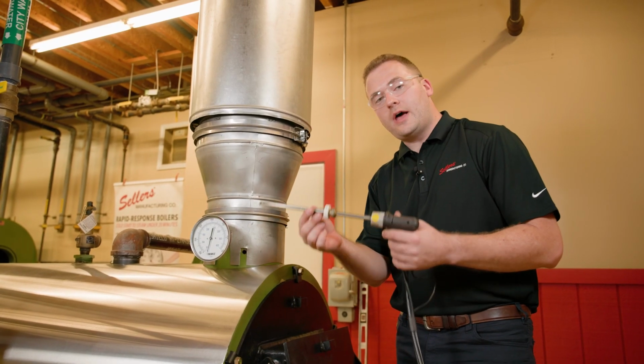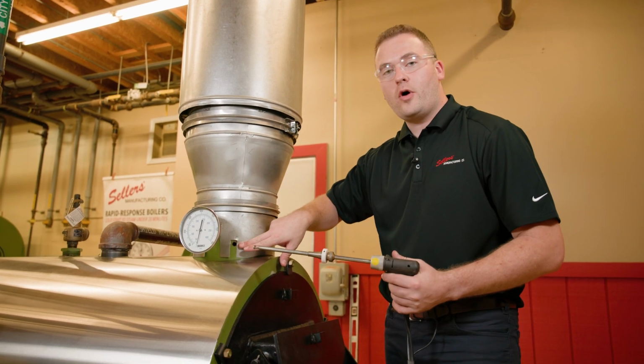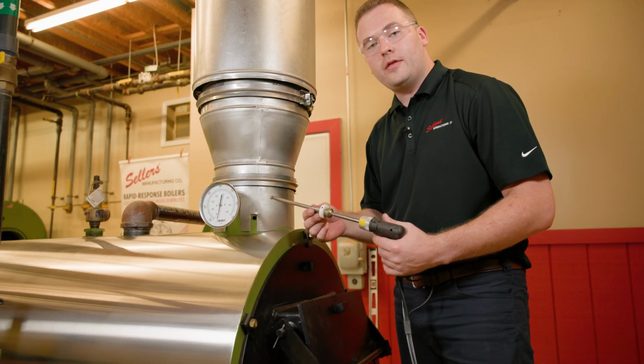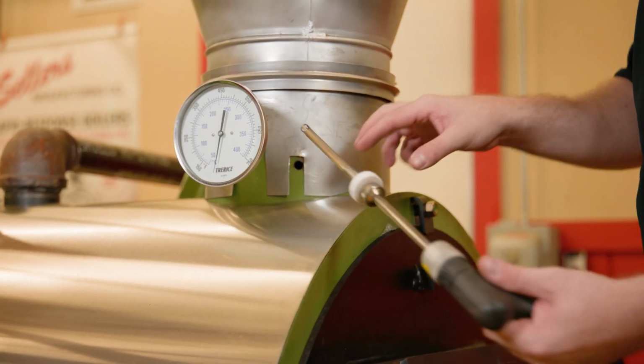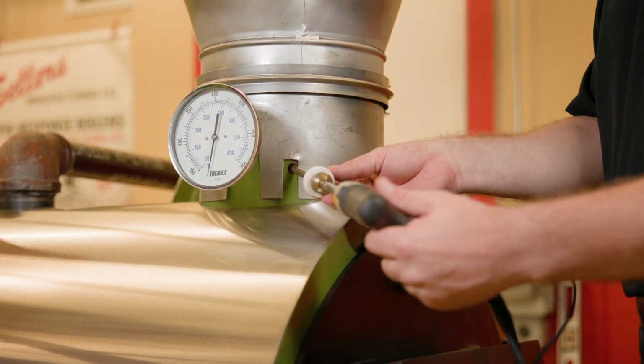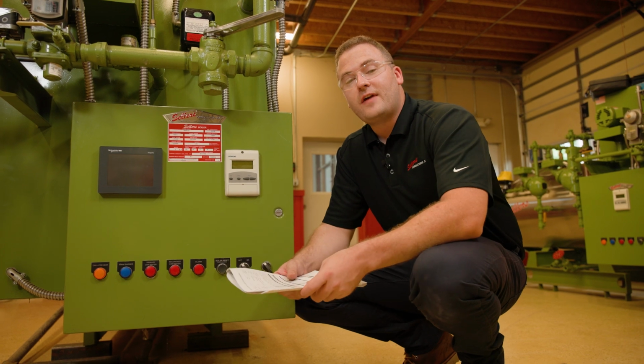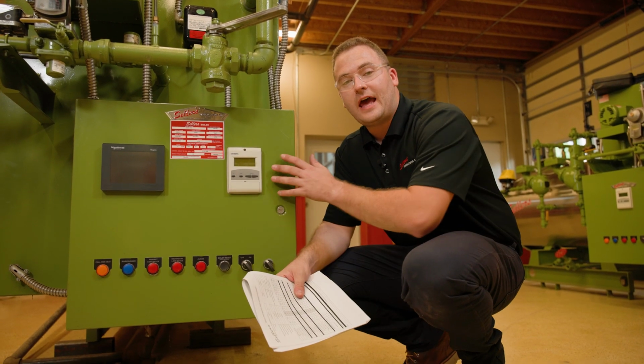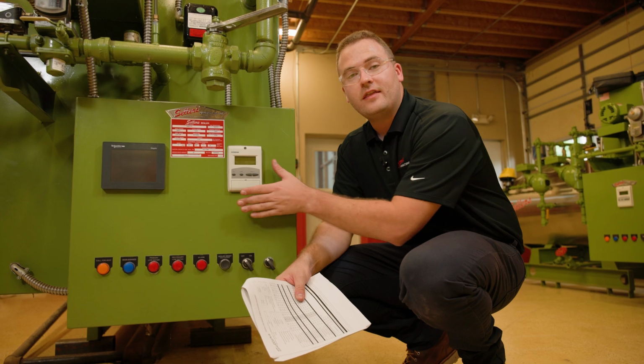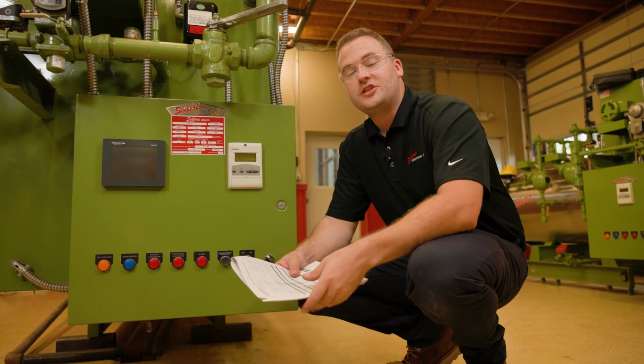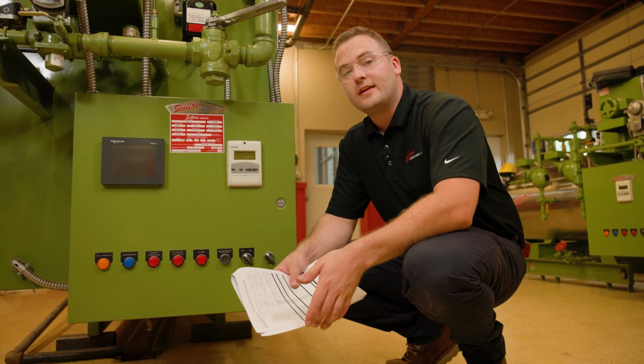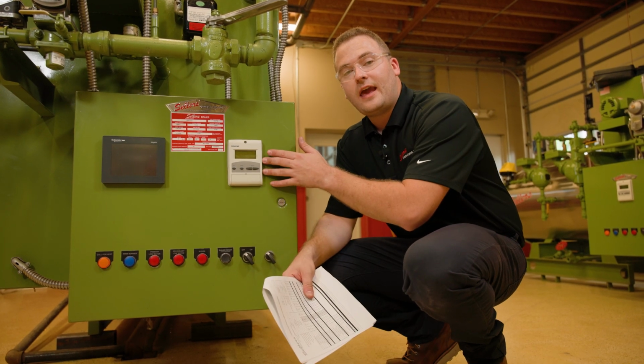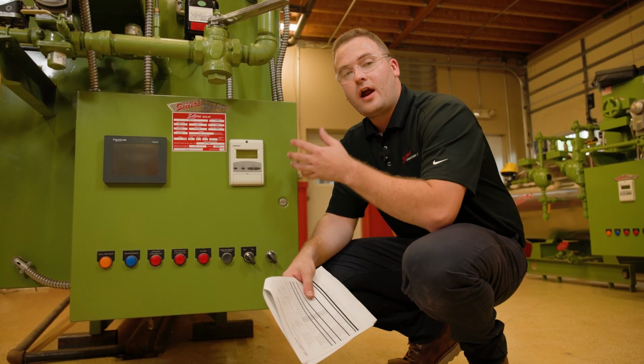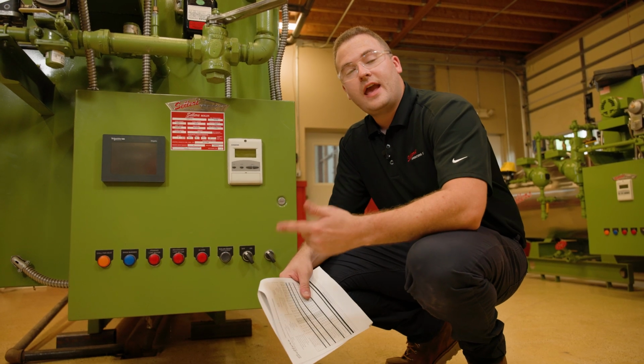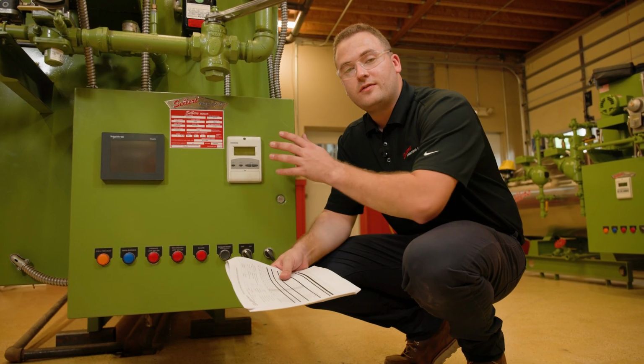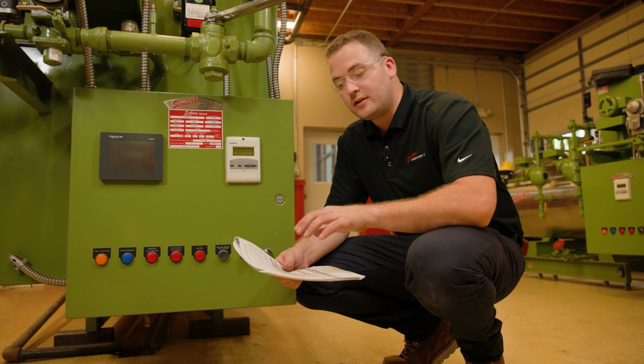Your combustion analyzer will have a measuring probe, and we're going to insert that probe into this stack connection on the rear of the boiler. Make sure that the probe length is set to be in the center of the stack for proper combustion measurement. Since this Sellers Manufacturing boiler is a modulating boiler, it's going to use the LMV5 system, and this AZL on the front of the electrical panel is how you're going to change the air damper and the fuel settings of the boiler. Inside the AZL, as you set the curve of the boiler, are going to be air damper settings and fuel valve settings, and you're going to transfer those settings after you set them up onto the factory test record.